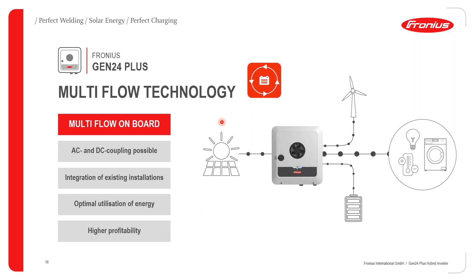So looking further at the possibility to retrofit the Gen24 Plus inverter into existing setups due to the multi-flow concept, we have a starting point whereby you could start with a Gen24 Plus inverter with a complete system. That means with its own PV array and a battery storage, and therefore you are able to take power from the PV side to charge the batteries. Then you can supply power from the batteries to your loads, or to export to the grid if this is allowable. In addition, due to multi-flow, the Gen24 Plus inverter is able to take a balance of power from the grid and recharge your batteries, if this is something that you'd like to configure your system to do.